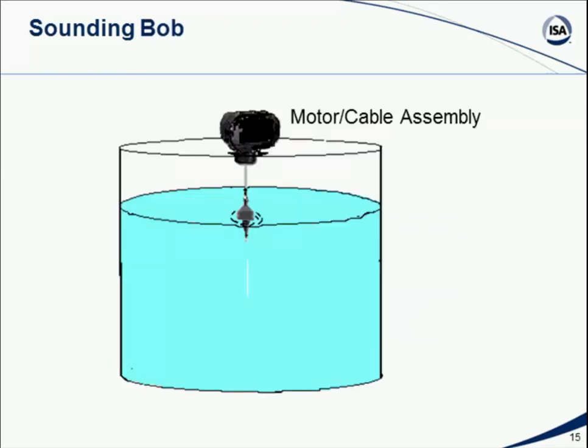Well, we probably don't want to have somebody go out every day, all the time, continuously with a dipstick and measure what's in most of our tanks. So, of course, through the years, automated mechanisms have been developed to make this a process that doesn't require human intervention. And one way this is done is with a motor cable assembly. And this is actually the same thing as Mark Twain would have used, except that instead of a human lowering a weight and realizing that the tension on the line just stopped because the weight hit bottom, a motor cable assembly can be used. And with a sounding bob motor cable assembly, there's a line with a lead weight or some other type of weight, but some device at the end of this that will cause the line to pull down, and we lower the line until the tension and torque on the line changes.